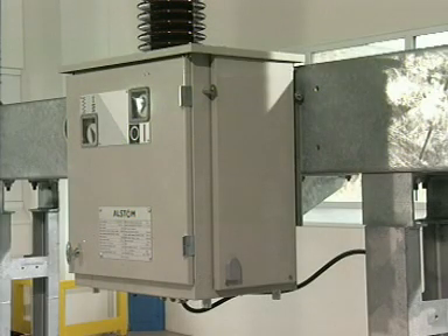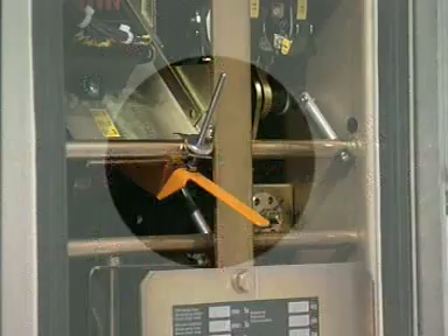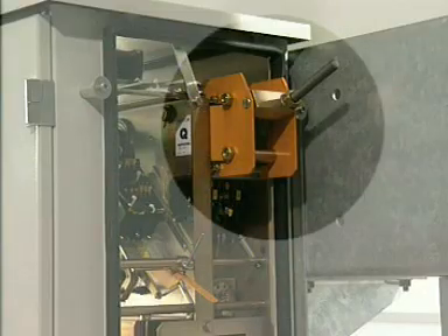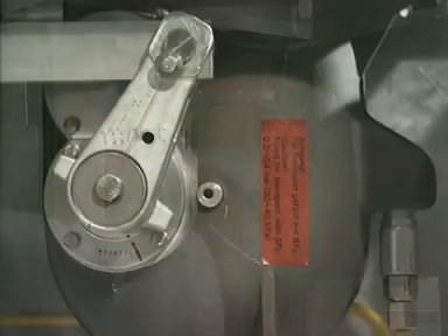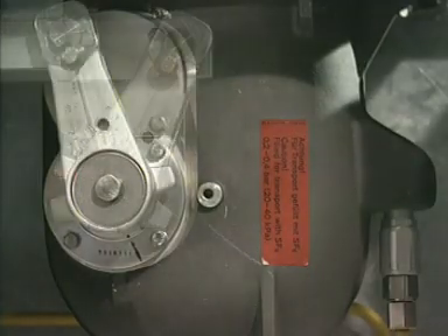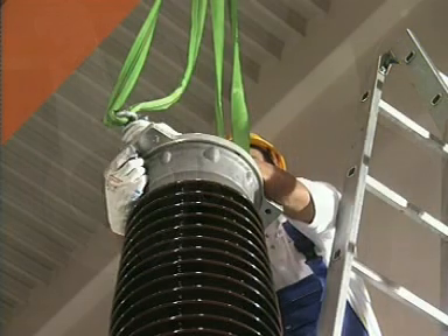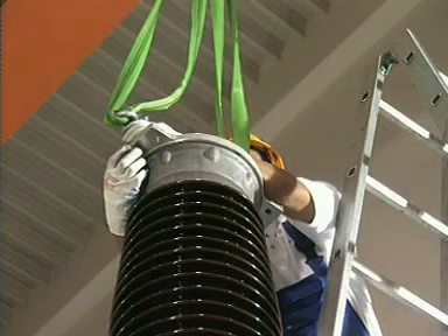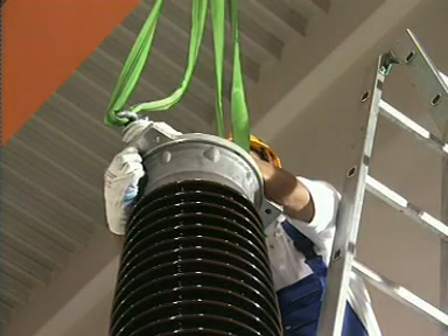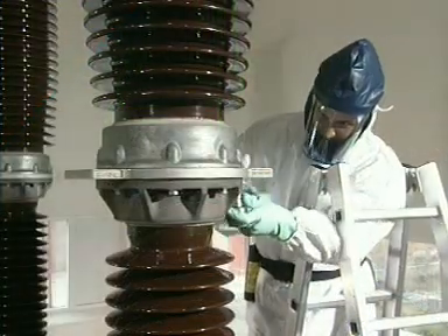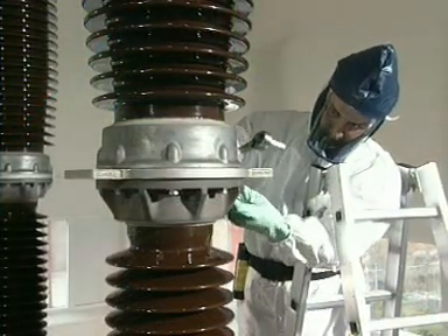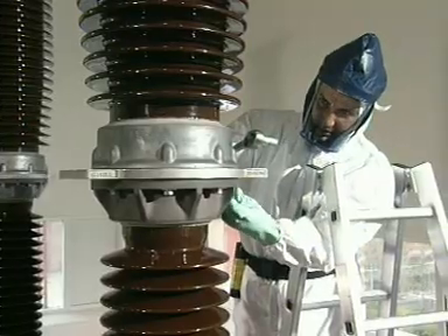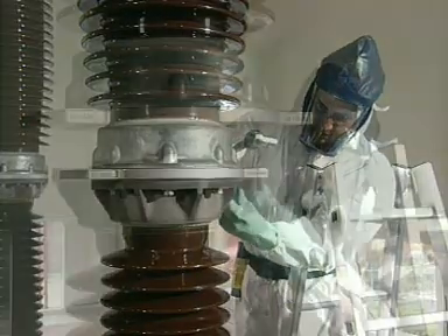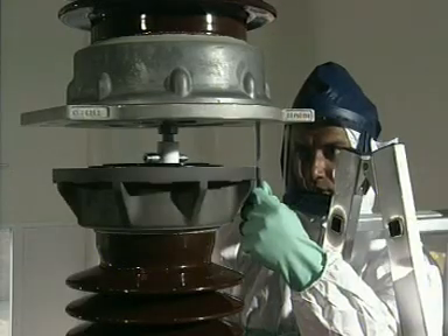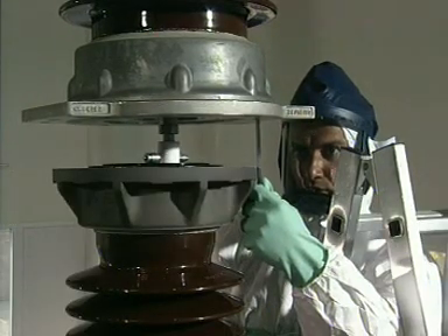Remove the right side cover from the mechanism. Install the blocking and low-speed operating device and move the circuit breaker to the closed position. Attach rope loops to the upper connection surfaces of the interrupter chamber. Loosen the bolts on the flange between the interrupter chamber and the support porcelain, and lift the interrupter chamber 80 millimeters.